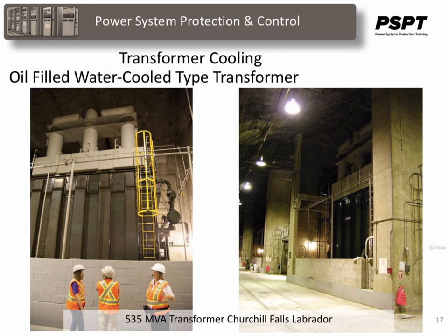Air from around the transformer's secondary leads is enclosed in what we call bus ducts, and the air is fan-forced through similar cooling radiators mounted externally. Cold water is forced to circulate through the radiators. This bus duct can be seen at the top of the transformers in each of these pictures.